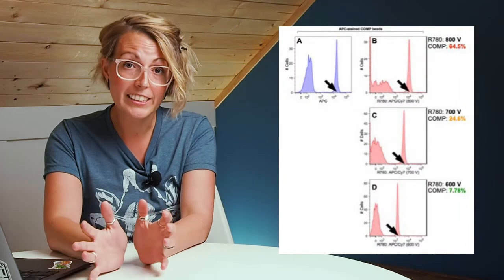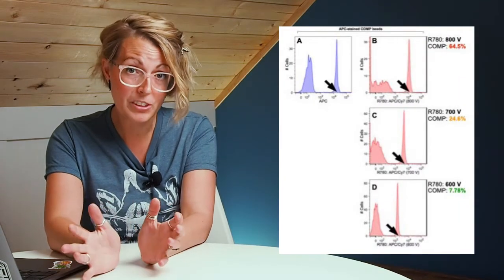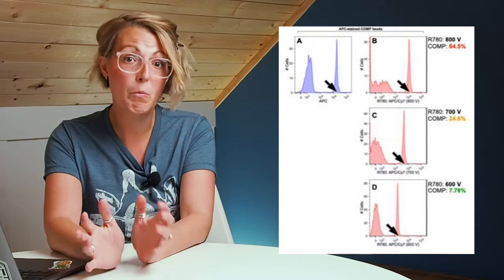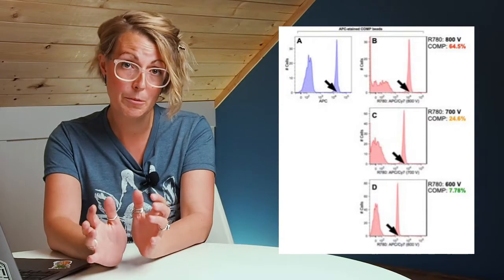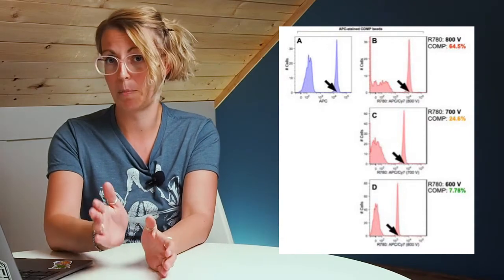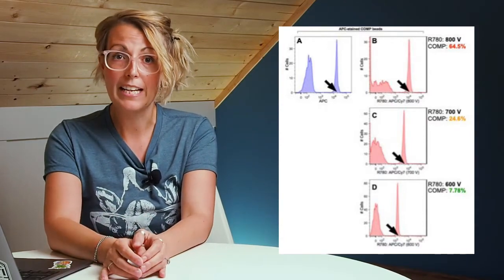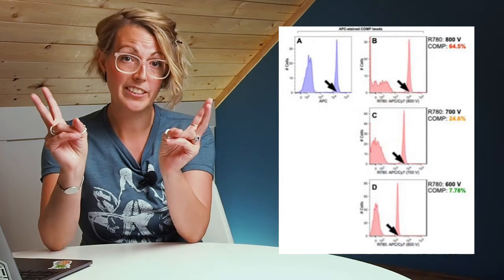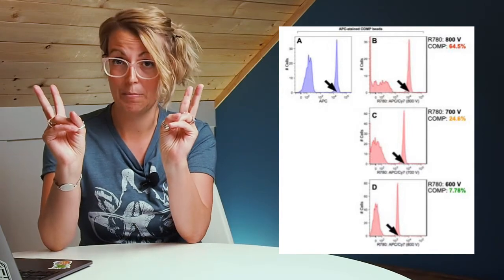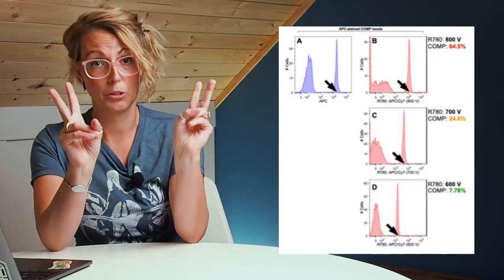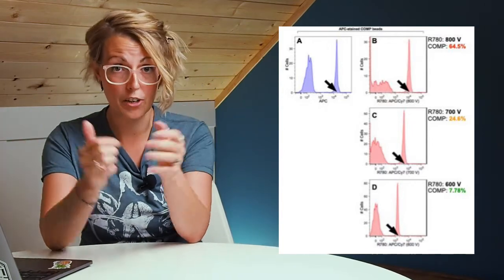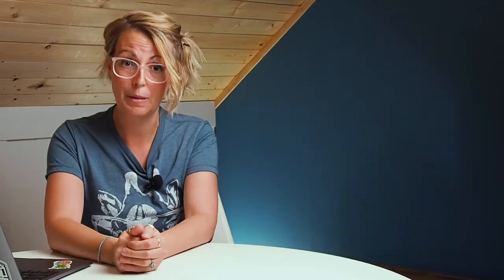So back to the original question: should I adjust my voltage to change my compensation? I have a twofold answer. If you have optimized your voltages, then no. Leave your optimized voltages. Adjusting your voltage at this point will reduce your ability to discriminate the negative from the positive. While it may decrease your compensation from high to low, whatever that arbitrary value may be for you, it will impact your ability to resolve your fluorochrome, which is never a good thing to do.